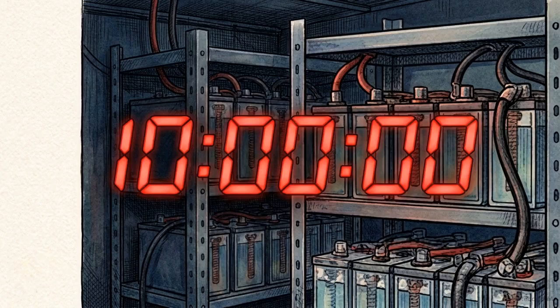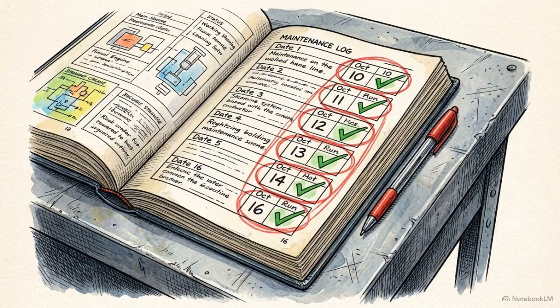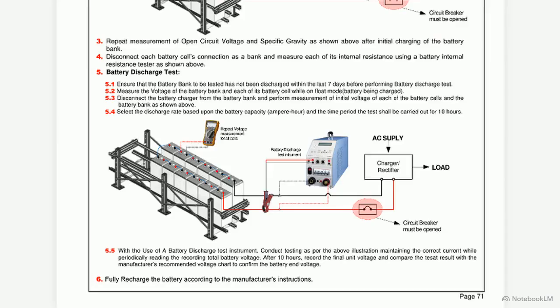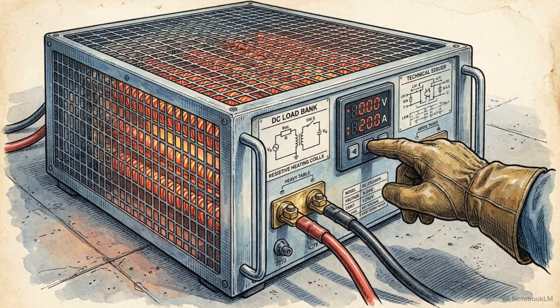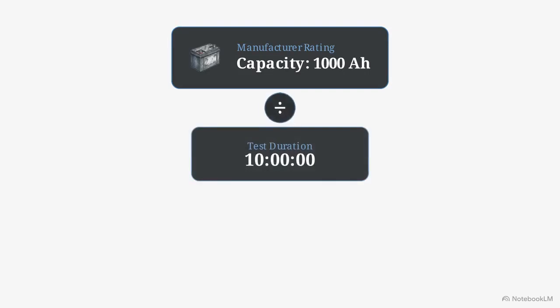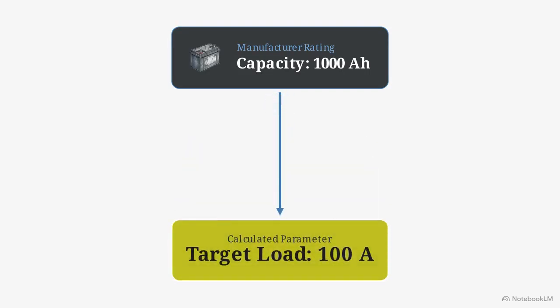To prove the chemical bank can sustain prolonged grid-down conditions, we run a 10-hour capacity test. But first, the operational log must confirm the battery bank has not been discharged within the previous 7 days. As shown in this discharge test diagram, absolute isolation is required. After measuring the initial float voltage, the charger must be physically disconnected from the battery bank by opening the circuit breaker. The DC load bank is connected, and its discharge rate is programmed. These parameters are strictly derived from the manufacturer's ampere-hour capacity rating, scaled for a 10-hour duration.